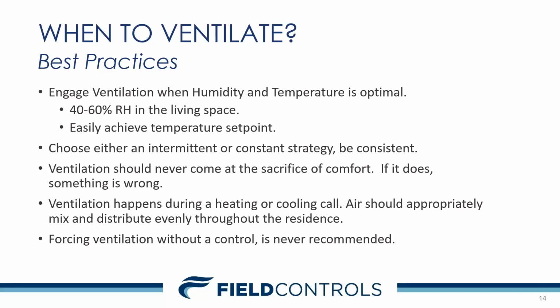Forcing ventilation without a control is never recommended. Typically, like you mentioned with the passive scenario before, if you just hardwire a damper to the air handler to open and energize whenever the fan turns on in the system, it overventilates the house and creates a multitude of problems.